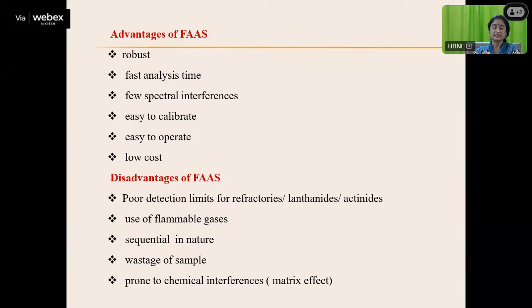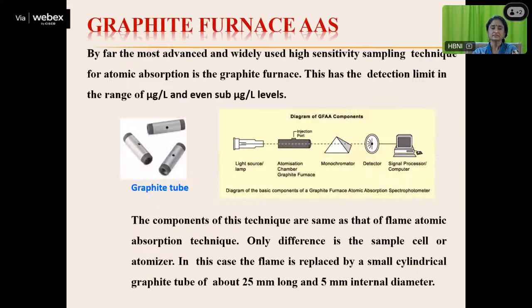Now, wastage of sample: in this case you are using a nebulizer, which forms the aerosol that is supplied to the flame for producing the atoms in a very efficient manner. But in this process, 90% of your sample goes to waste. Only 10% gets atomized. So wastage of sample is very high. It is also prone to chemical interferences, as the temperature is very low. Just now we have seen a few examples.